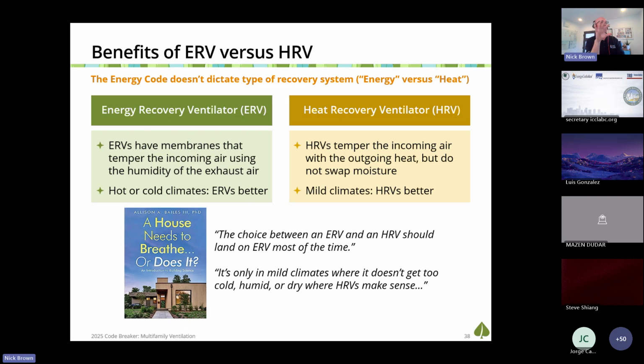I asked him about this constant debate in green building circles on ERV versus HRV. Again, the energy code doesn't care, but the difference is that ERVs have membranes that allow some humidity through them, whereas HRVs do not. They're only swapping heat. And the book says the choice between an ERV and an HRV should land on ERV most of the time. It's only in mild climates where it doesn't get too cold, humid, or dry where HRVs make sense. Those happen to be the climates you all work in, don't they? So again, I tell my clients, I don't think you need to worry too much about that ERV, HRV decision. They're both going to serve your building pretty well.